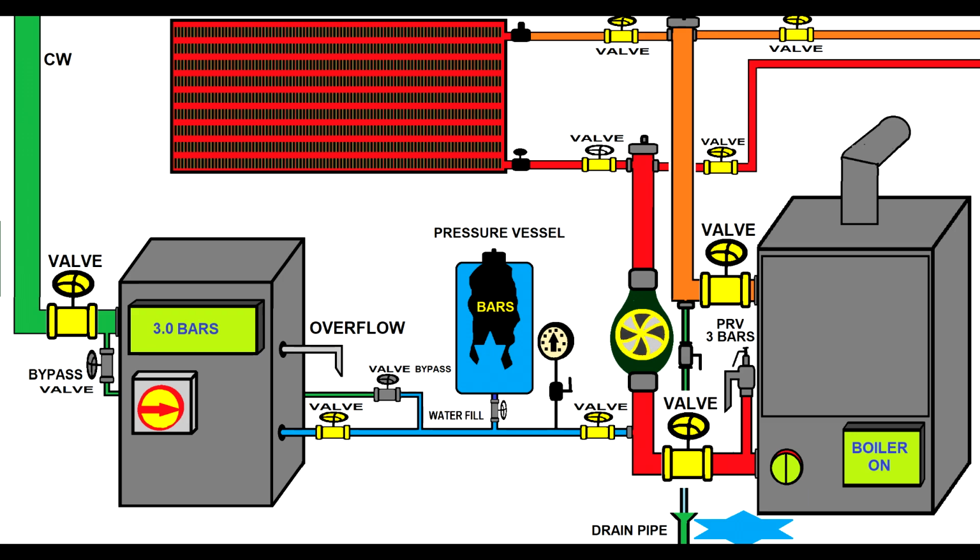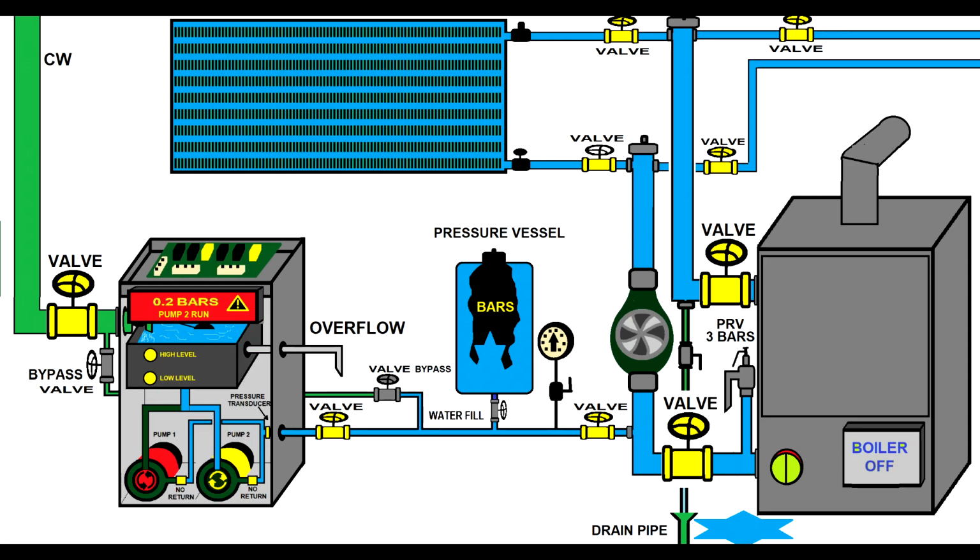And after you lose enough water, obviously the heating system won't run. You'll have a flooded service floor or plant room. In the morning, obviously the pressure will drop again, and the pressurization will compensate again. But let's say you're unlucky, and both pumps will die, not just one pump. Both pumps will be damaged.